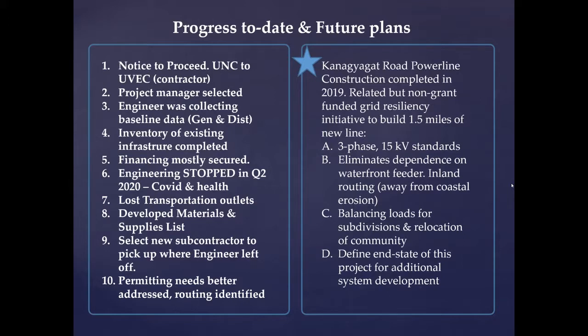So the short-term goal of increasing the voltage here was that whenever there's a lot of wind on the system, almost always from a pure load or energy demand standpoint, the village ought to be able to run on one single diesel generator plus the wind. The generator can move up and down based on how much load and wind are varying. But right now we're not seeing that. So that's really the goal of the power line voltage expansion, and that should address the major issues.